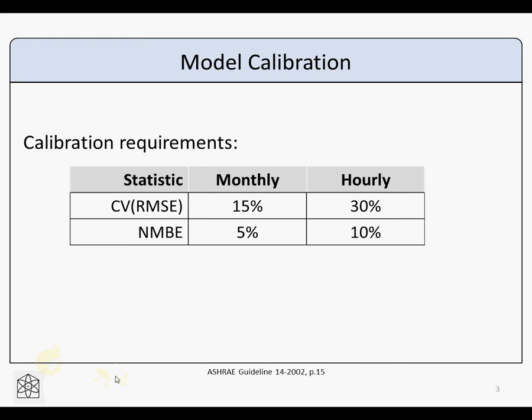One note I will make about this is that it means that your model is matching the utility data of the building. It is possible that there is another set of parameter combinations that also describes this. So this is why you'll want to do this on your steam use, electric use, and chilled water if you have it, rather than just total energy use, because you could conceivably come up with a way that you could match the total energy use, but you wouldn't really actually be predicting which end uses in your building, say plug loads versus the heating load, were causing that.